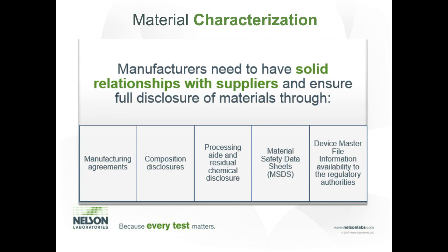So you're going to sterilize it possibly. You're going to package it. You're going to clean it. You're going to mold it. Whatever you're going to do can impact that biocompatibility. So the device master file helps you with the initial risk of that material, potentially, depending on what tests are in there. But it will not end your biocompatibility assessment.